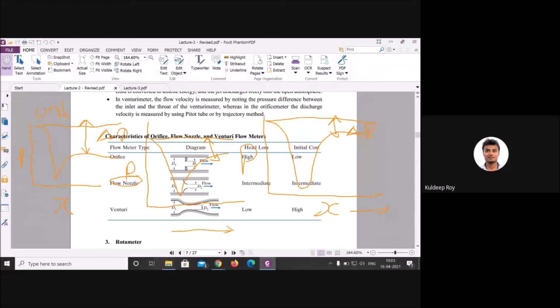So generally, if you are looking for the head loss, here it is written intermediate, means neither low nor high. So it is between this. If we're talking about capital cost, initial cost, in the case of Venturi, as I already told, the capital cost is very high because you want to design a smooth divergent, convergent angle, and it requires much more theoretical study. But in the case of orifice, the capital cost or initial cost is very low, and here the head loss is very high. And for the flow nozzles, the head loss is intermediate, and the capital cost is also between that.